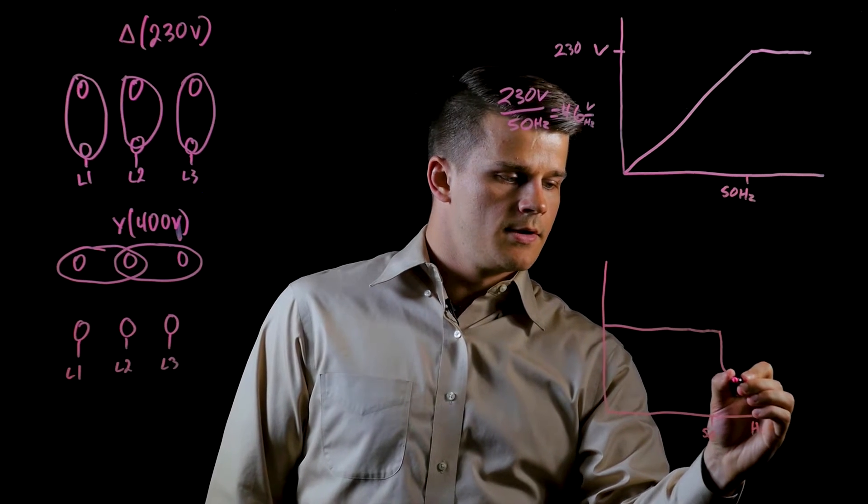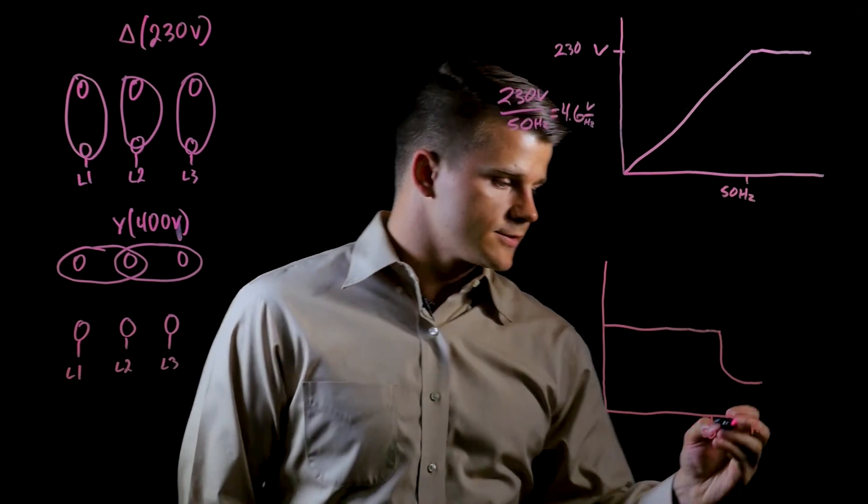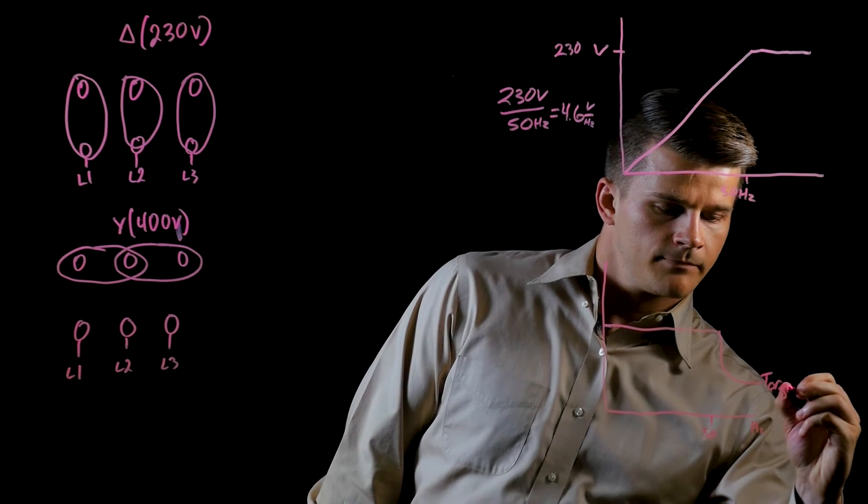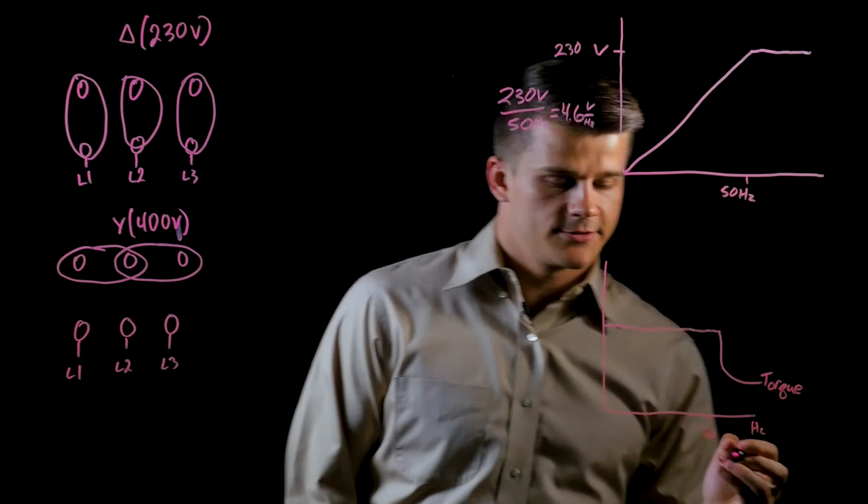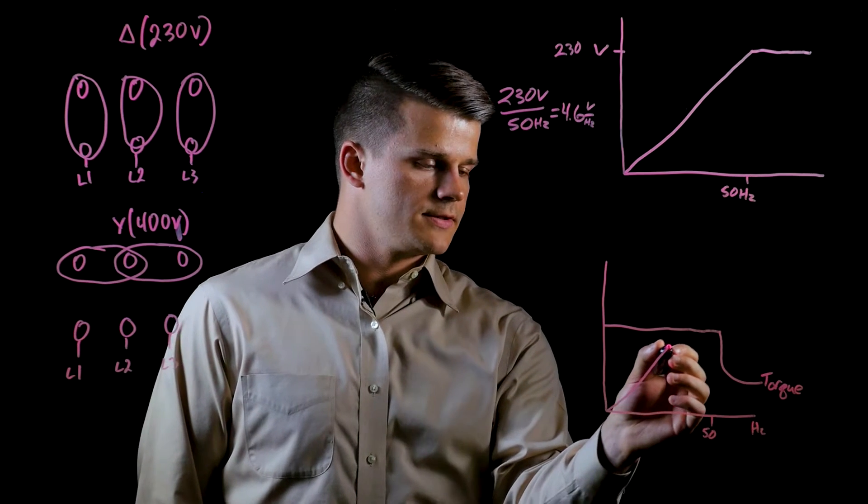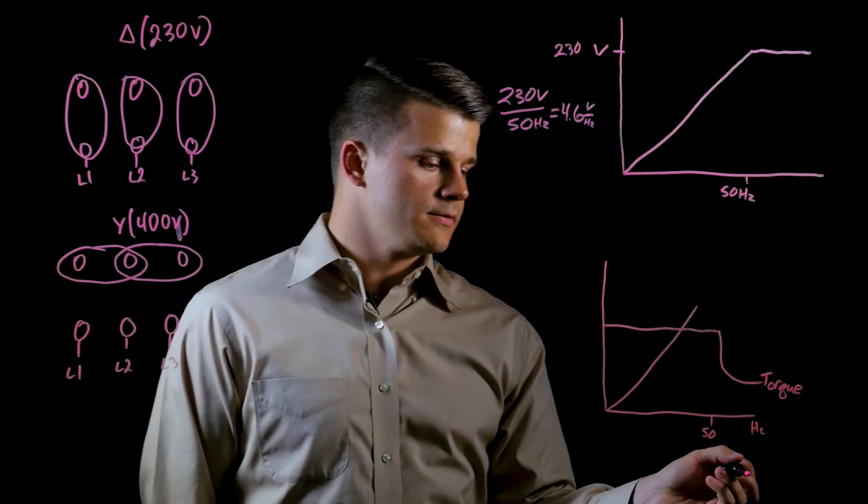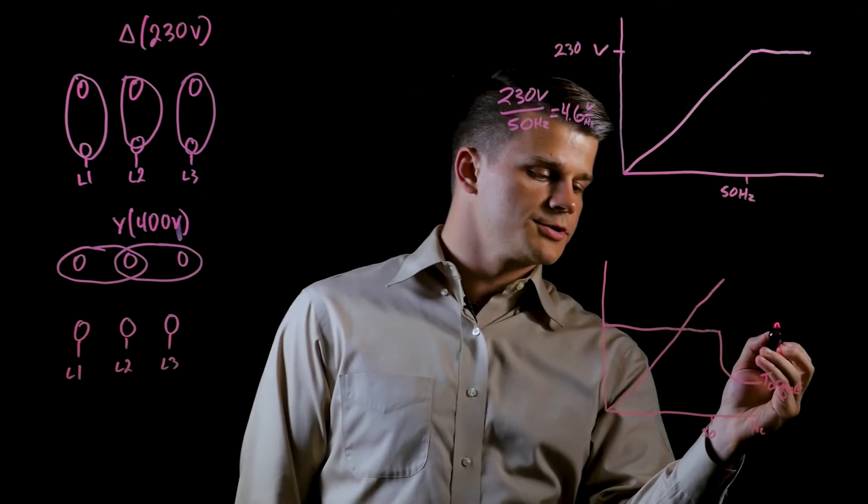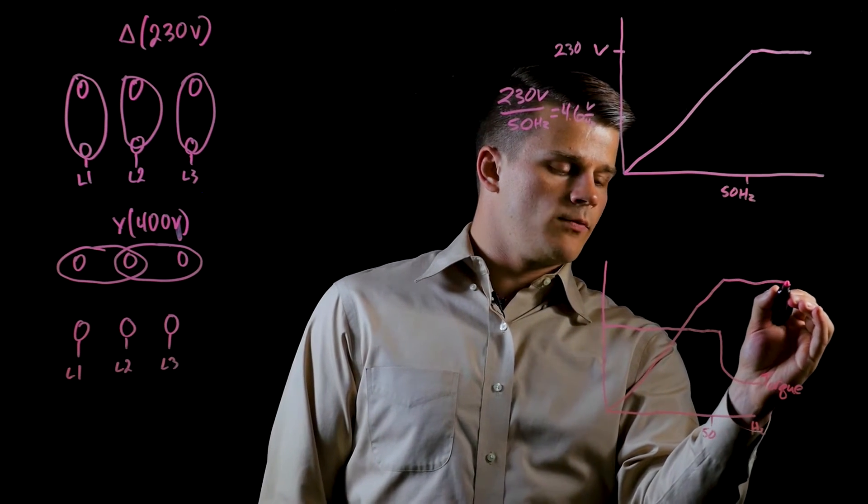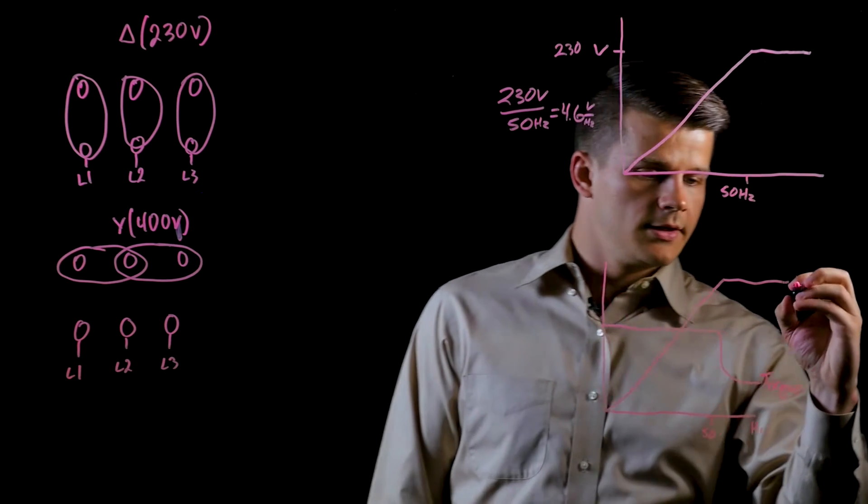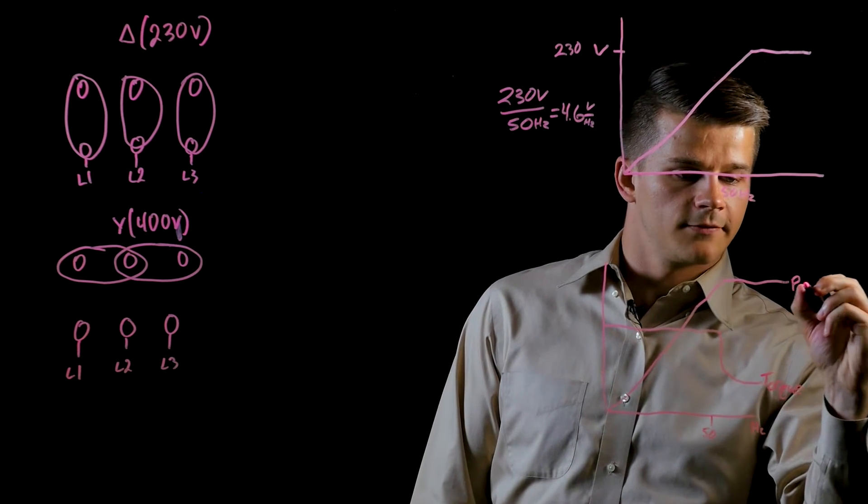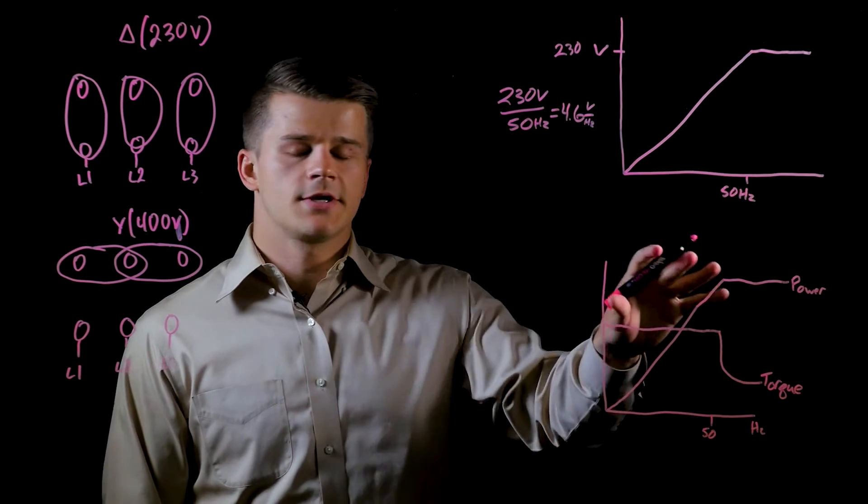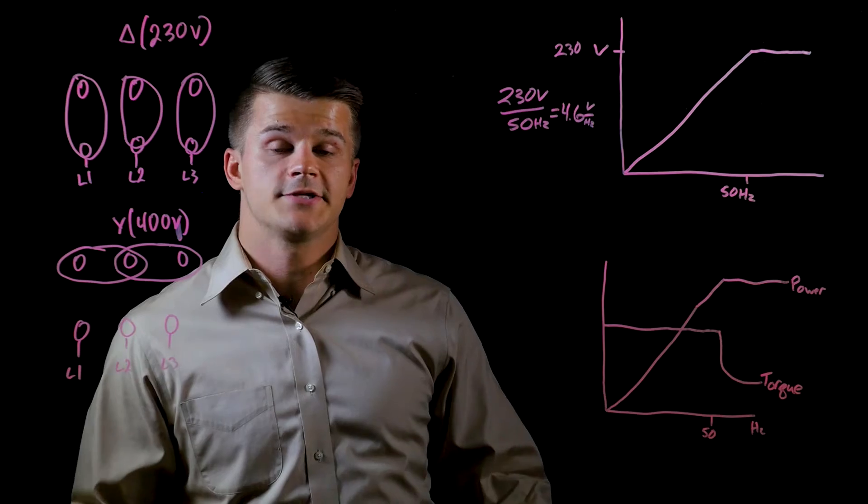In this case, your torque decreases inversely proportional to the frequency in the field weakening range. For power, that increases proportionally up to 50 Hertz, and then once we get past 50 Hertz, it stays constant. That's your power in standard operation. Now we'll talk about the 87 Hertz trick.